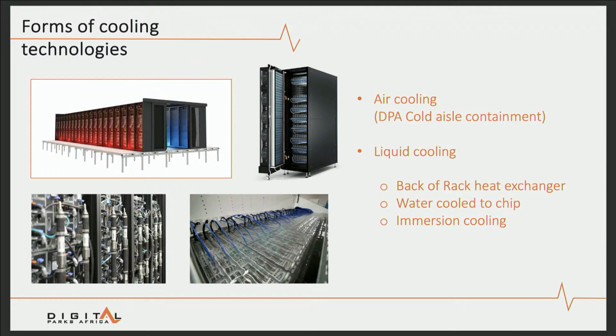So what cooling technologies do we have currently available? I think we are all familiar with the air cooling that we currently see in the data centers. And over the years that has been optimized. What we have now is the cold aisle containment concept that really makes sure that the cold air stays where it's meant to be, that it doesn't mix with the hot air that's coming out the rear side of the servers, and that really cooling is applied only to those areas where it needs to be applied within a data center environment. And we are seeing that that type of cooling is reaching its limitations.